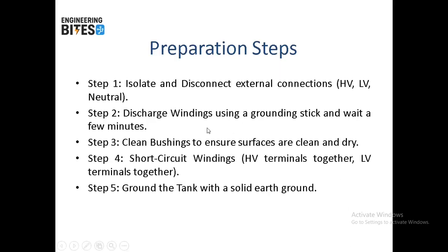We have 5 steps. The first step is to isolate and disconnect the external connections, high voltage and low voltage connections. Step 2, discharge windings using a grounding stick and wait for a few minutes. Step 3, clean bushing to ensure surfaces are clean and dry. Step 4, short circuit windings, the high voltage terminals together and the low voltage terminals together. Step 5, ground the tank with a solid earth ground.